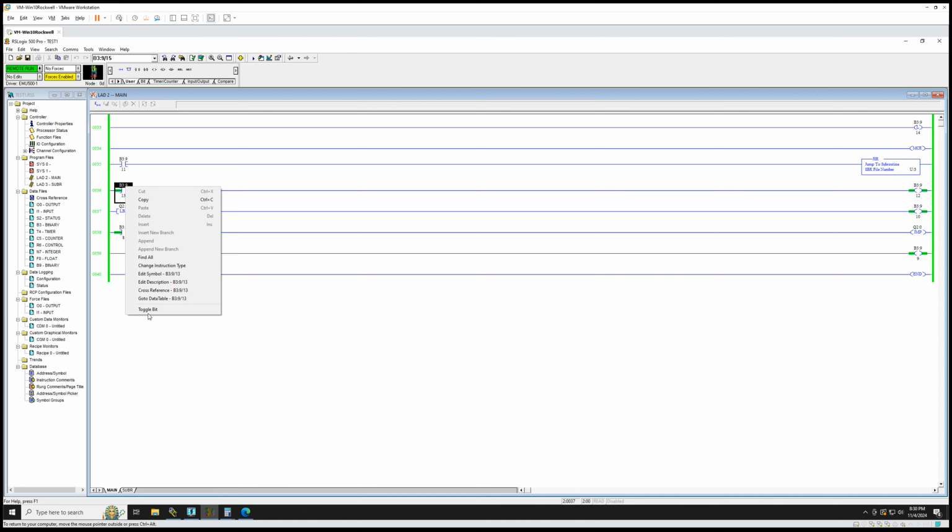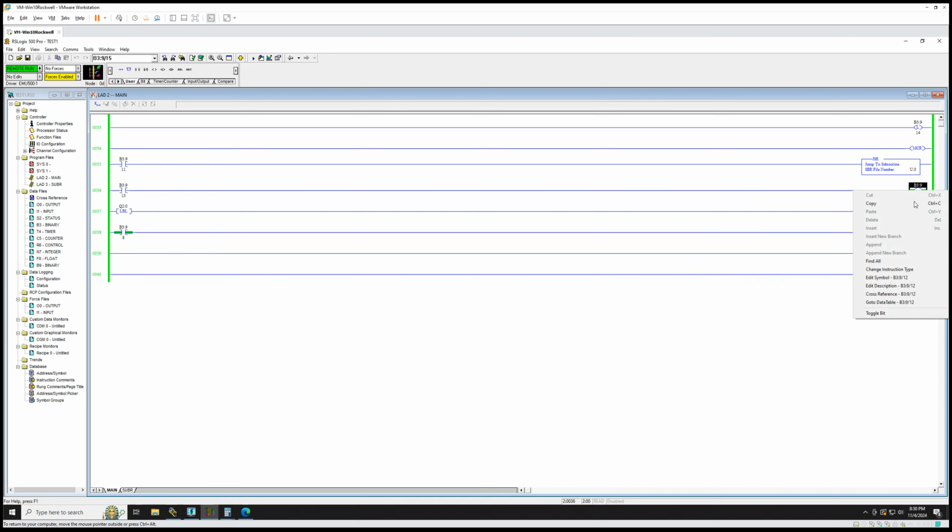So nothing else is being scanned. So if I want, I can turn off everything I want in the program. You see how when I turn this off, this did not go off because it's not being scanned. And I can turn everything off. So right now what's happening is program came down and it's stuck in a loop that nothing's happening. You can add some conditions in the middle. Once all the conditions are met, you can go out of your jump, and so you don't create a circle loop for itself and there is no output of the whole program. This can throw you off if you don't know how you set it up.